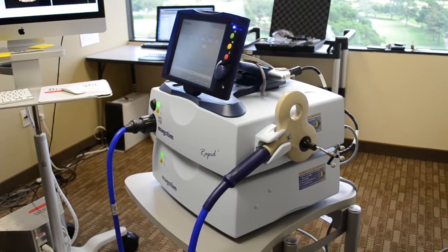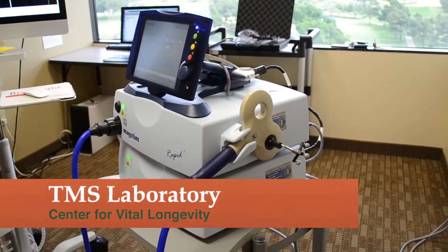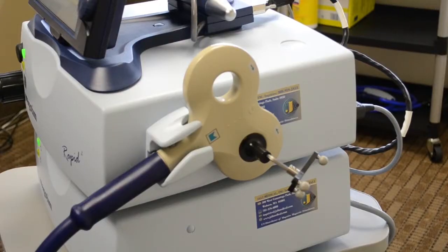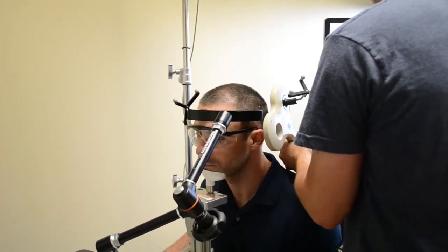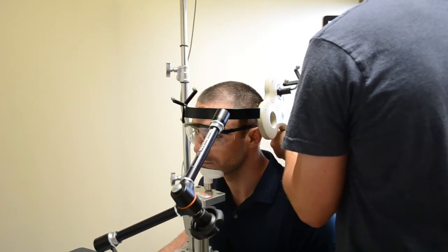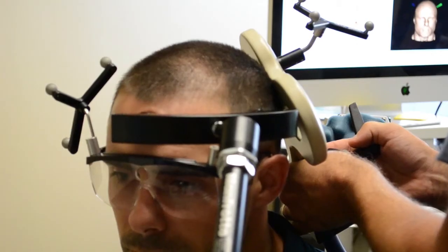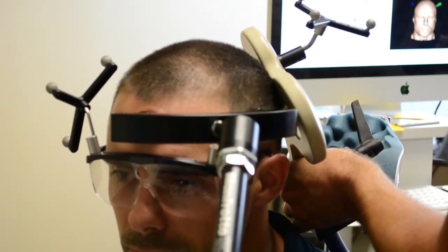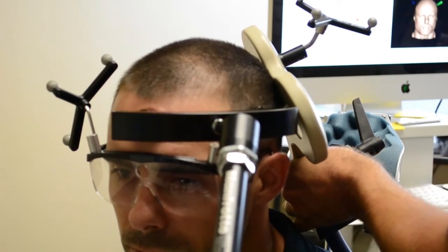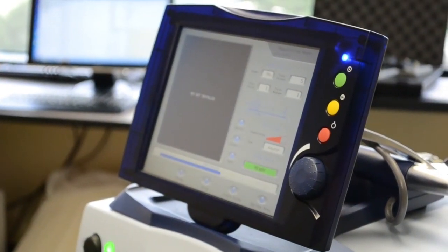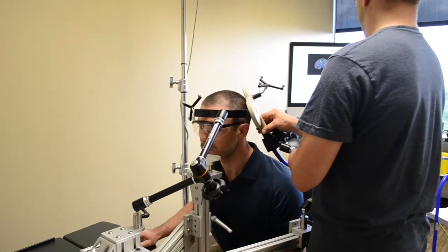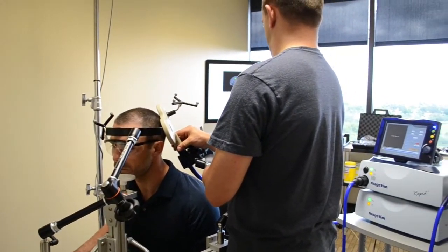TMS involves the delivery of brief magnetic pulses to a small region of the brain through a figure-of-8 shaped coil. The coil is placed on the head and positioned over the brain region that we're interested in. The coil delivers a very brief magnetic pulse, which makes a click sound, or a short train of pulses that can be heard going click, click, click. These pulses stimulate brain activity in the region under the coil.